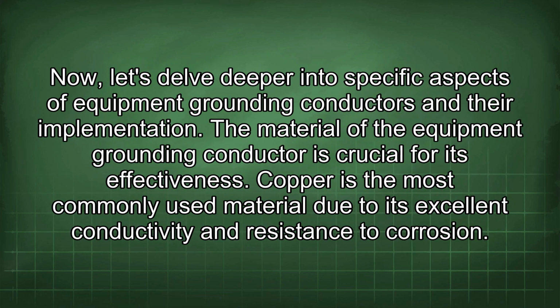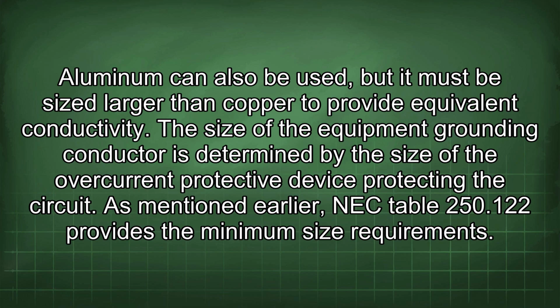Now let's delve deeper into specific aspects of equipment grounding conductors and their implementation. The material of the equipment grounding conductor is crucial for its effectiveness. Copper is the most commonly used material due to its excellent conductivity and resistance to corrosion. Aluminum can also be used, but it must be sized larger than copper to provide equivalent conductivity. The size of the equipment grounding conductor is determined by the size of the overcurrent protective device protecting the circuit. As mentioned earlier, NEC Table 250.122 provides the minimum size requirements.